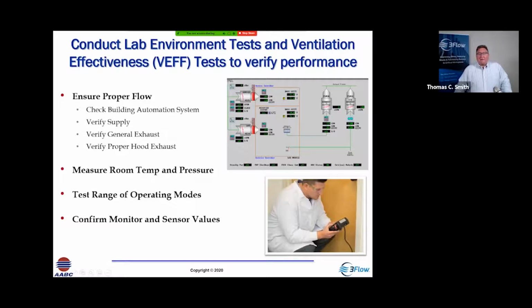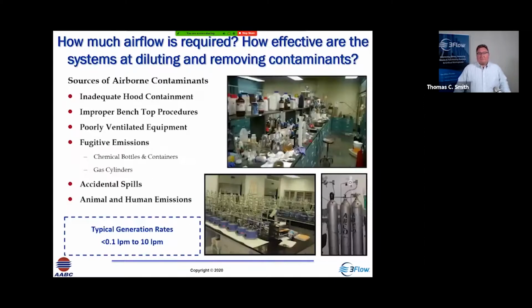We can look at proper pressurization. We can confirm that the room is properly balanced and that the building automation system is reporting the same as we measured within some expected tolerance. And so this gives us the ability to do a more holistic evaluation.